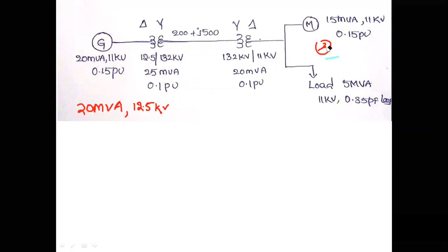Now I'm selecting the base values of the entire system, given by 20 MVA and 12.5 kV. Now see here, I'm obtaining xg1 new. So xg1 new is equal to old per unit. What is the old per unit value? 0.15, multiplied by what is MVA base new? New is equal to 20.